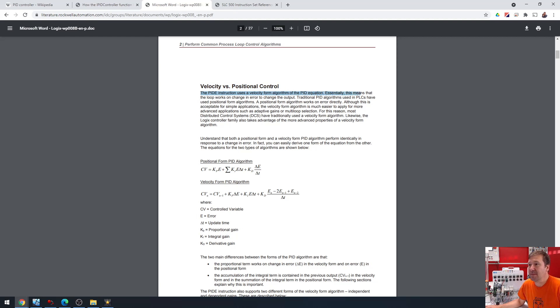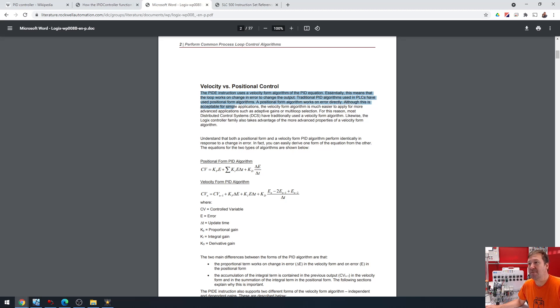Essentially, this means that the loop works on the change in the error of the output. Traditional PID algorithms used in PLCs have used positional form algorithms. A positional form algorithm works directly on the error.